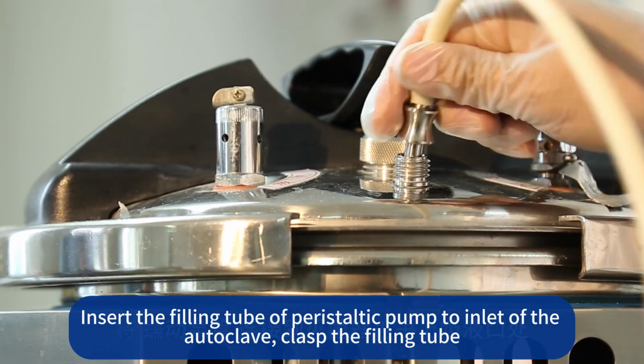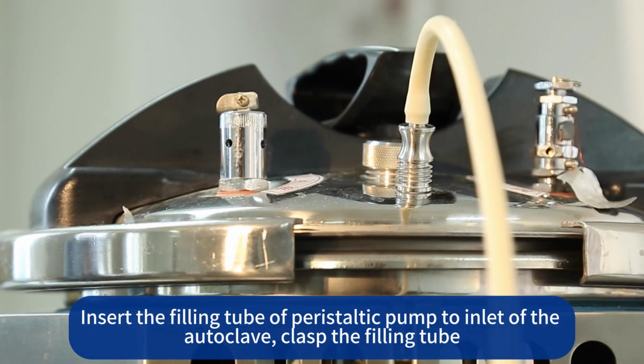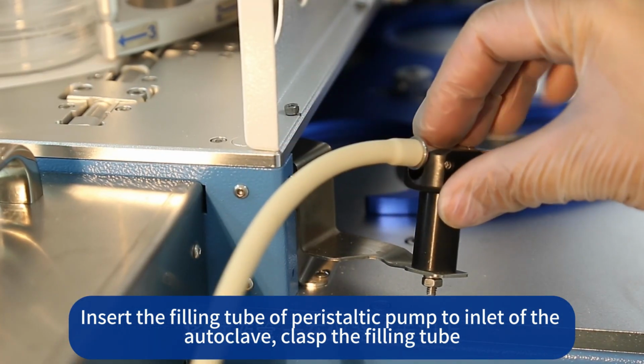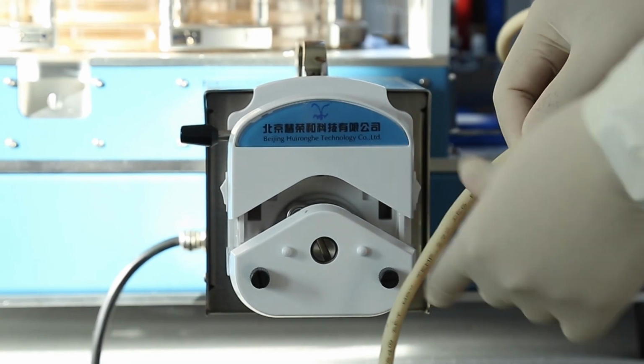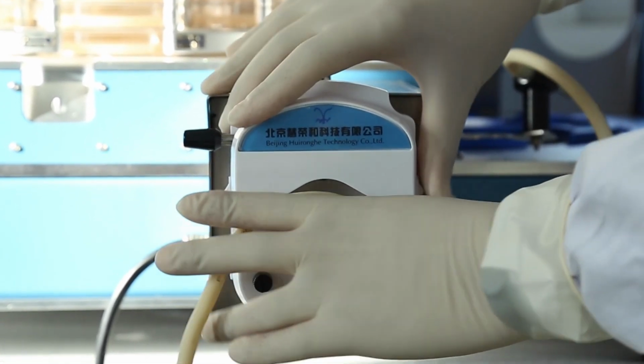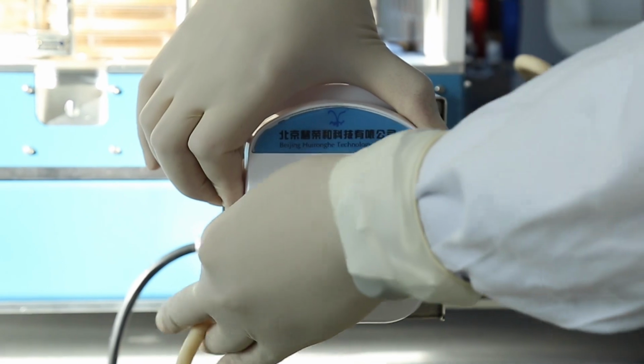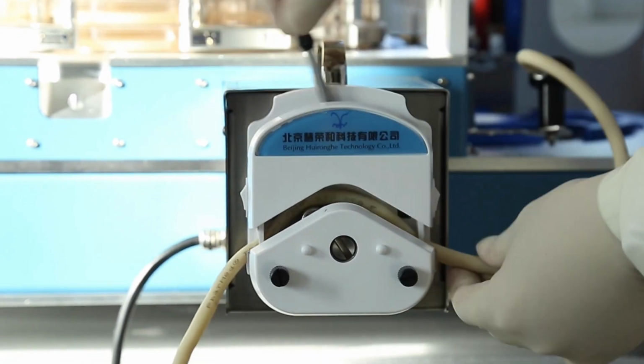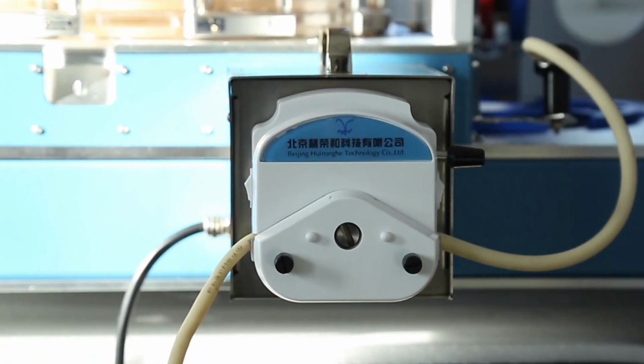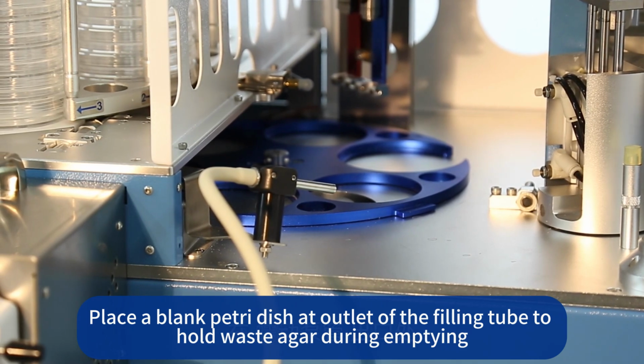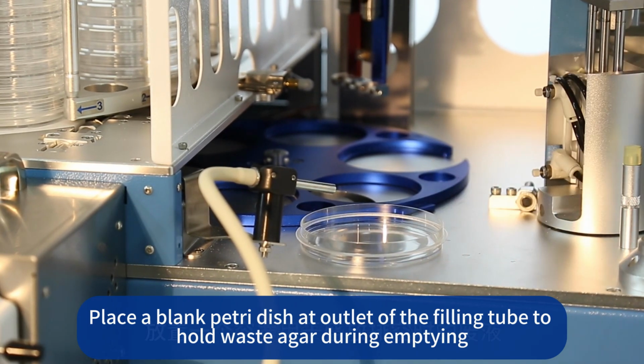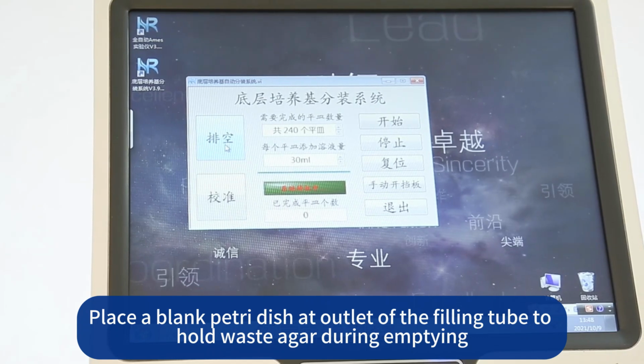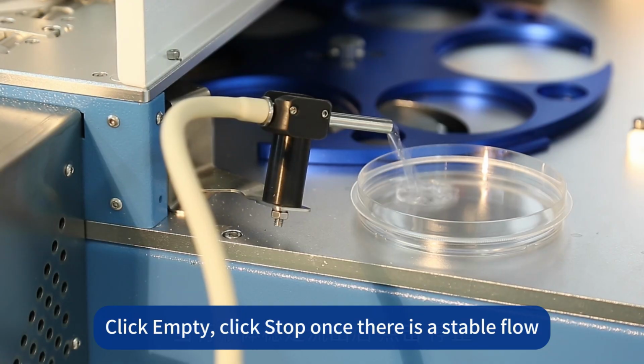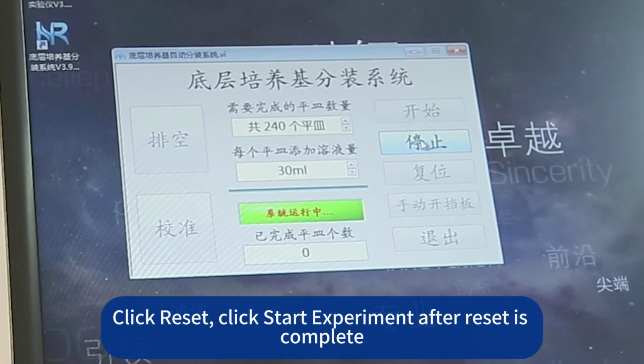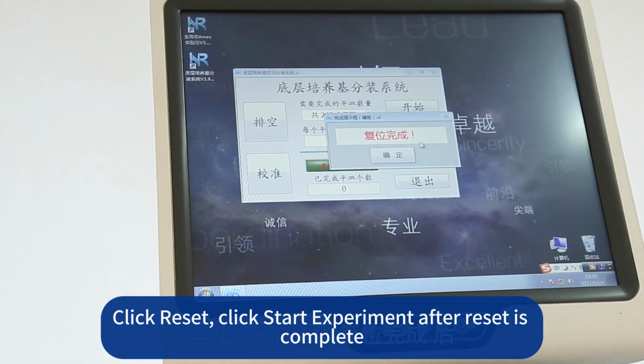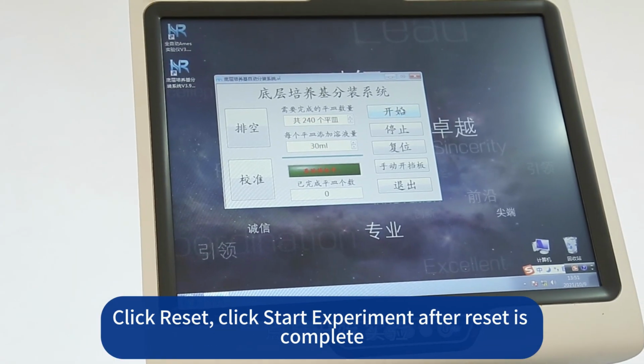Insert the filling tube of peristaltic pump to inlet of the autoclave. Clasp the filling tube. Place a blank Petri dish at outlet of the filling tube to hold waste agar during emptying. Click Empty. Click Stop once there is a stable flow. Click Reset. Click Start Experiment after reset is complete.